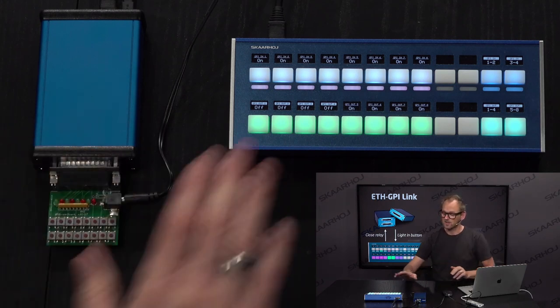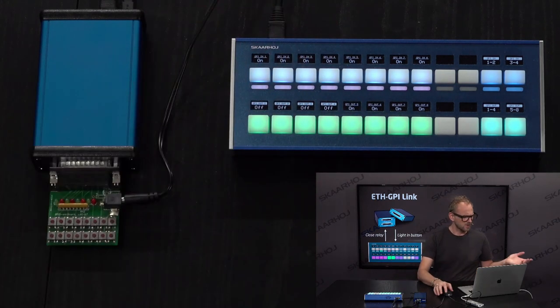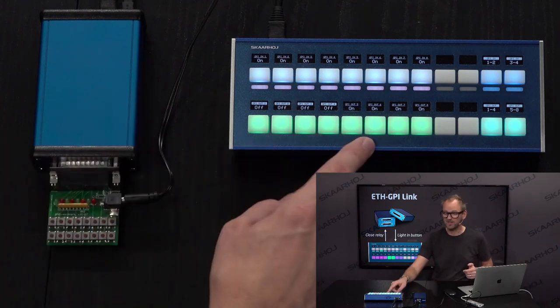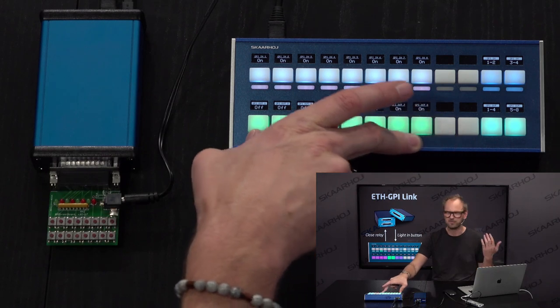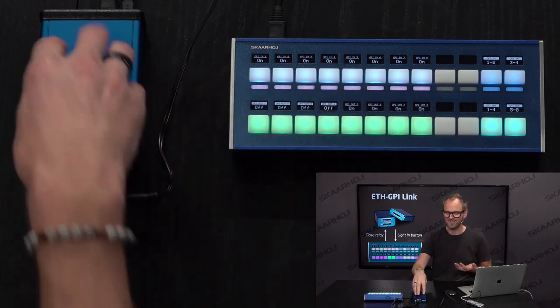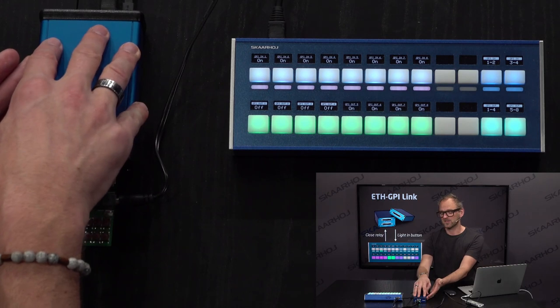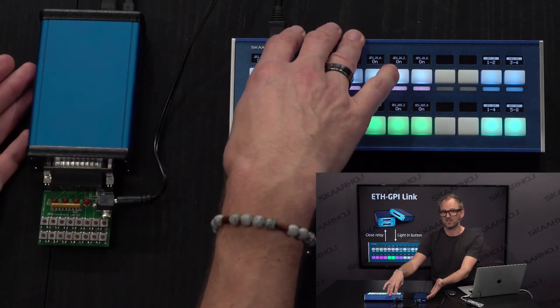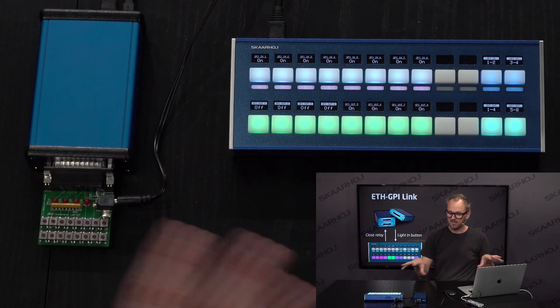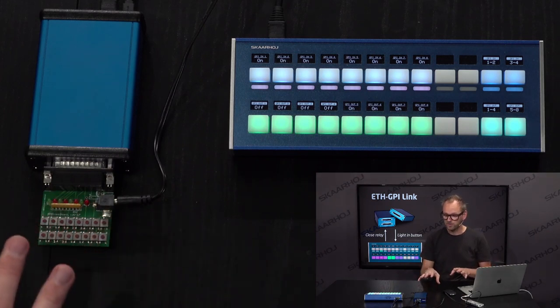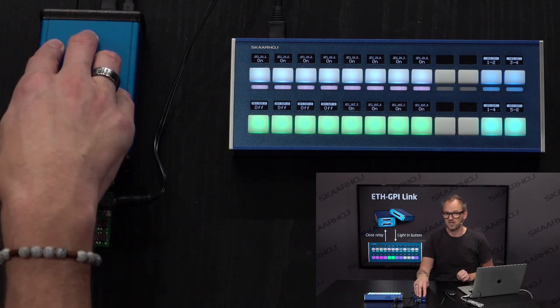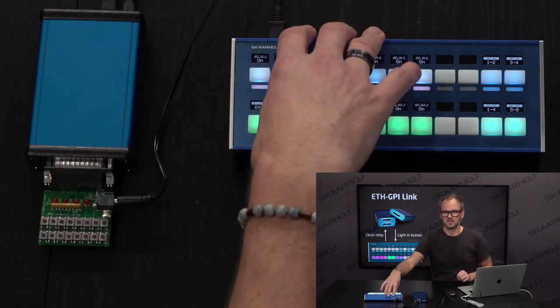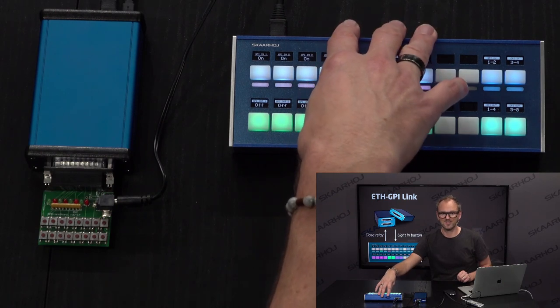These two boxes are connected to each other over Ethernet. This one is the server, so it has a TCP server built in. This is an Ethernet client. When this one boots up, it's trying to connect to the IP address of the panel, and basically the way this works is that this box has been instructed to listen to a number of registers, binary registers over here.